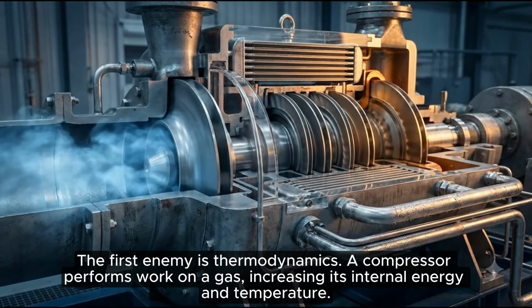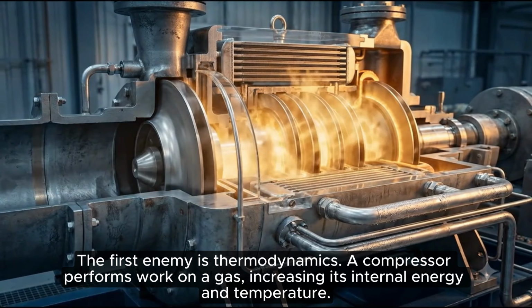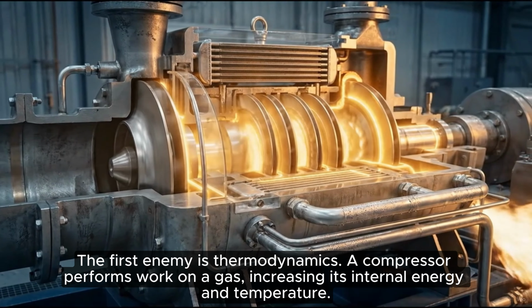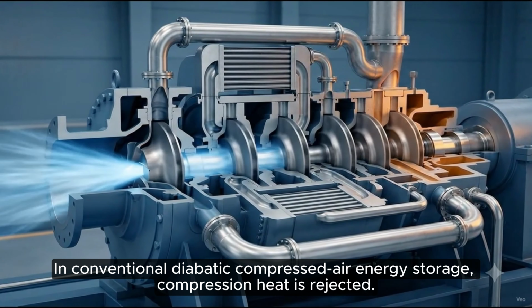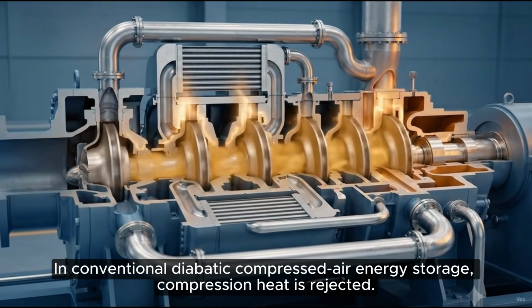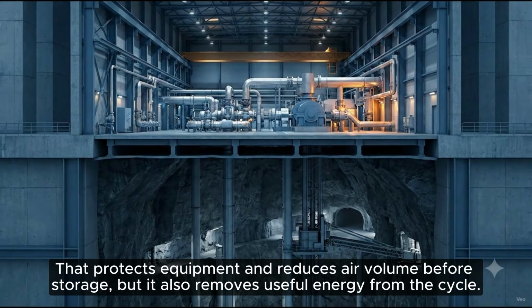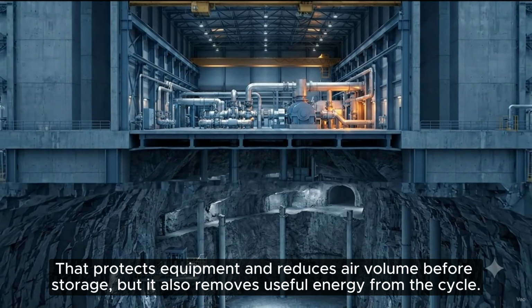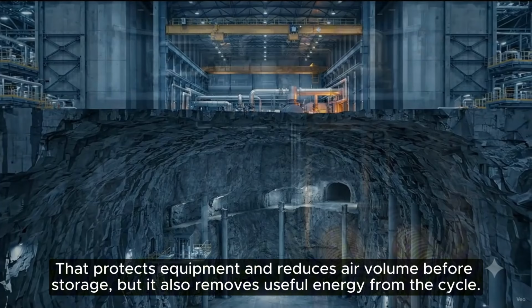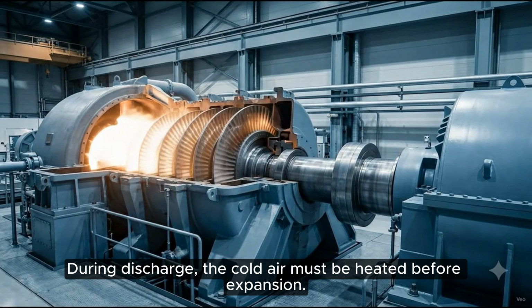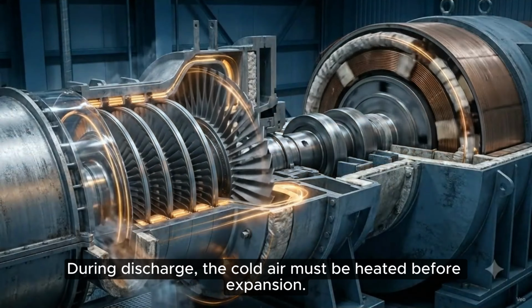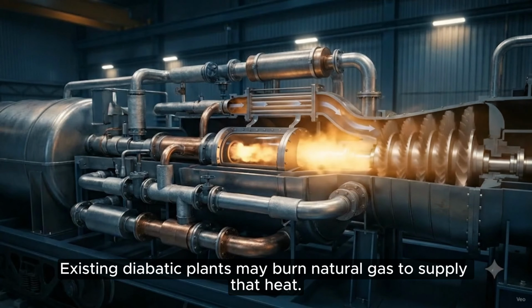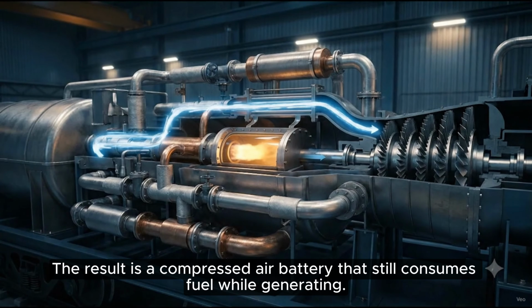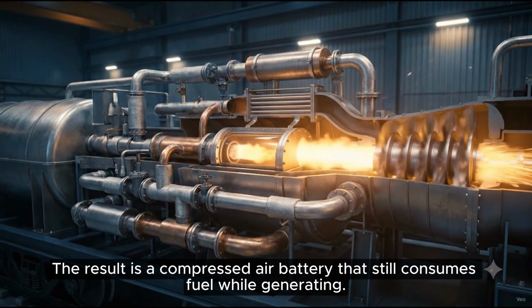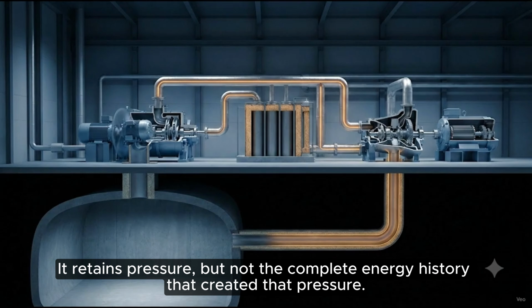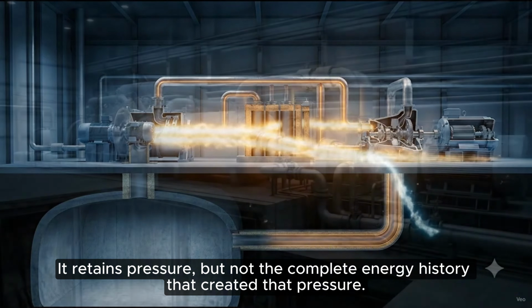The first enemy is thermodynamics. A compressor performs work on a gas, increasing its internal energy and temperature. In conventional diabatic compressed air energy storage, compression heat is rejected. That protects equipment and reduces air volume before storage, but it also removes useful energy from the cycle. During discharge, the cold air must be heated before expansion. Existing diabatic plants may burn natural gas to supply that heat. The result is a compressed air battery that still consumes fuel while generating. It retains pressure, but not the complete energy history that created that pressure.